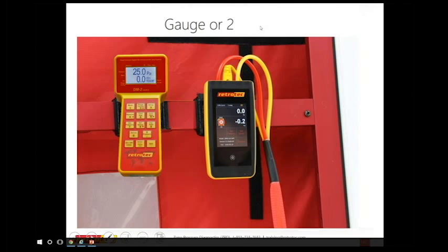Exactly. So the idea being that we can use 1 gauge to run the blower door and do a reference from the fan to the outside to make sure that the house is depressurized at 50 and no environmental factors have changed that. Meanwhile, you can actually just move around freely with a 2nd gauge and take those tests intermittently. Bill, any view on that, perspective on that?